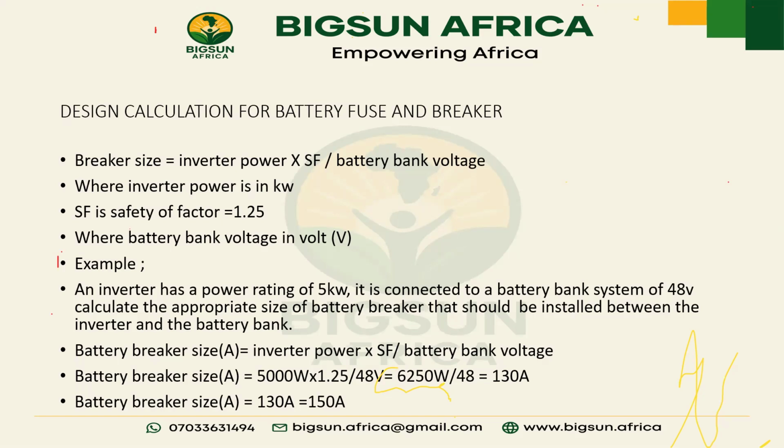Yes, the reason you are having the 3 banks is because you want the inverter to pull this current over a longer period of time. It's not pulling them instantaneously. So it's the same. You are working with the voltage of the bank, not the amperage or how many banks there are. Okay.